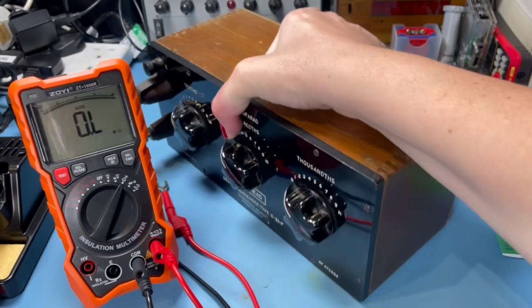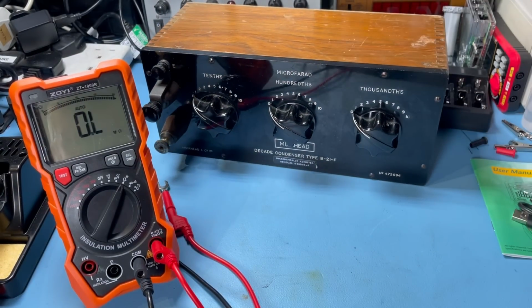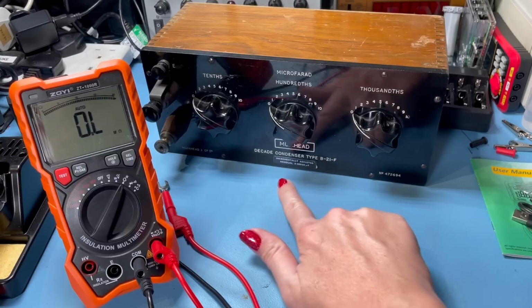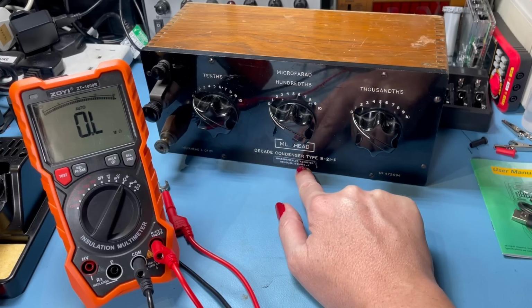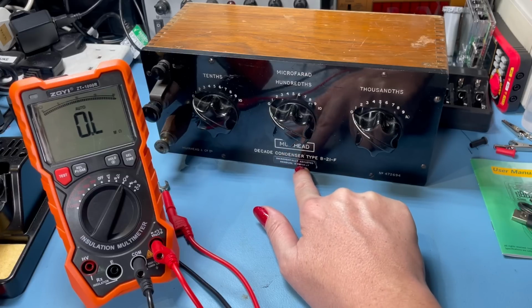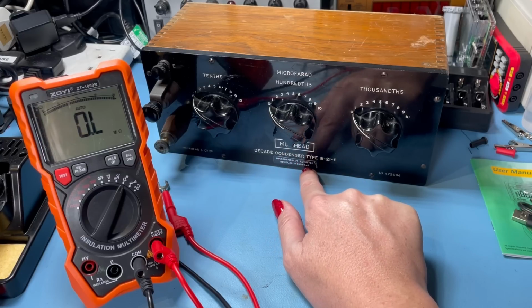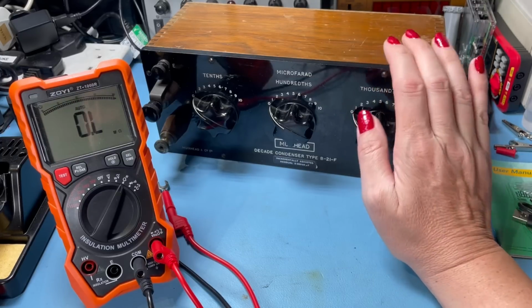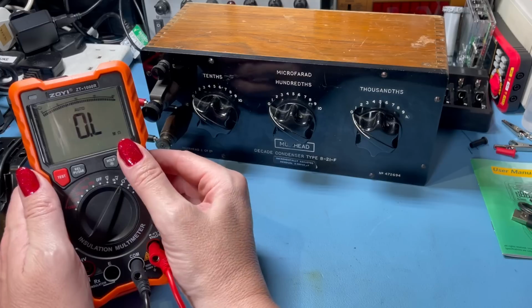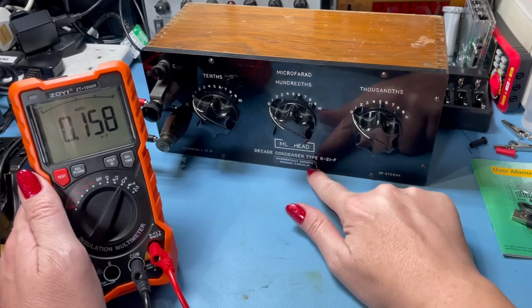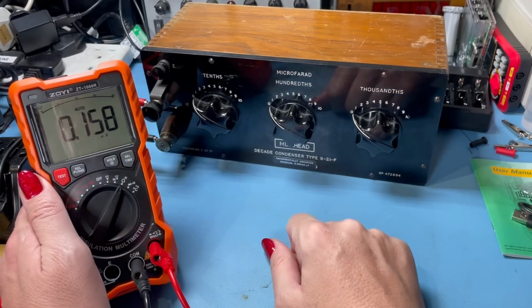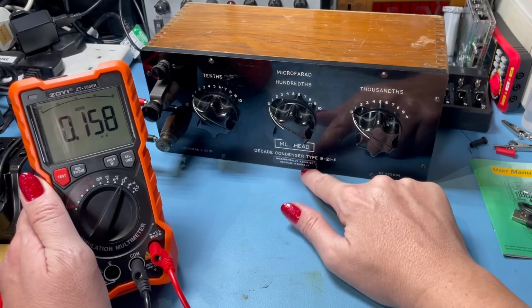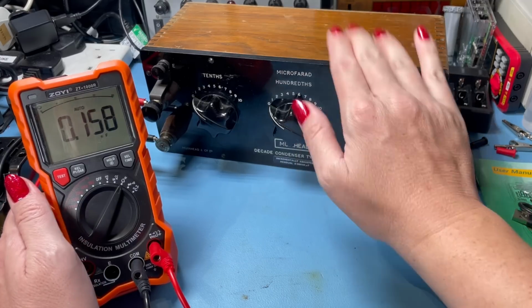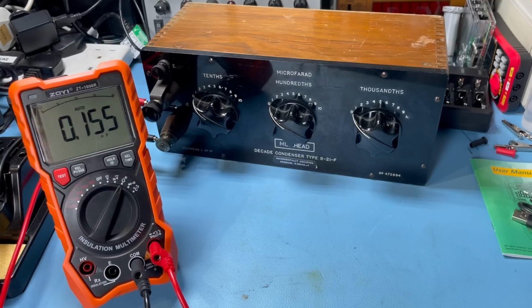Now, in terms of capacitance, I've got this Muirhead decade box here. Recently I had the Zoyi DQ02 LCR meter on test, and what I will say is it picked up the residual of this decade box. It has a residual of 160 picofarads, and the LCR meter did pick up that 160 picofarads. Capacitance mode. Do you know what? It's doing it. Look at that. 160 picofarads is the residual of this box. That's not bad at all.